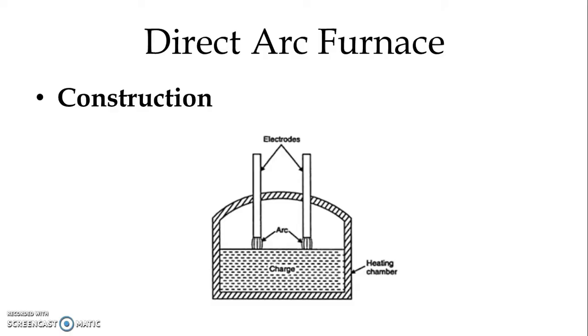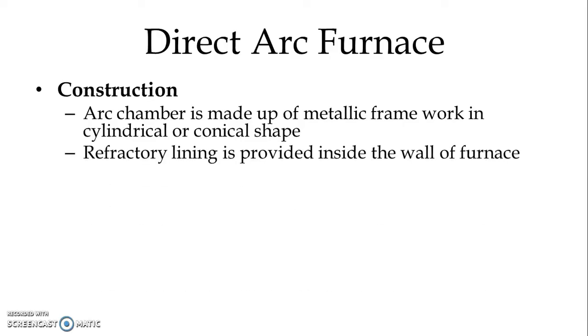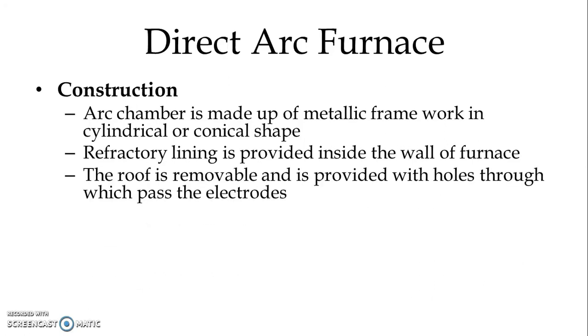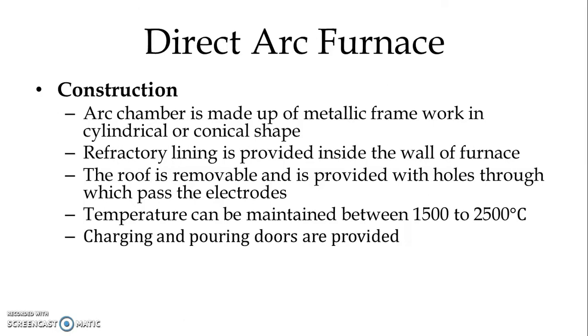We can see the direct type of Arc Furnace in the figure. We have two electrodes for single phase. We have a heating chamber and charge is filled in the furnace. The arc chamber is made up of a metallic framework in cylindrical or conical shape. Refractory lining is provided inside the wall of the furnace. The roof is removable and is provided with holes through which electrodes can be passed. We use electrodes made from carbon or graphite, and electrodes are replaceable.